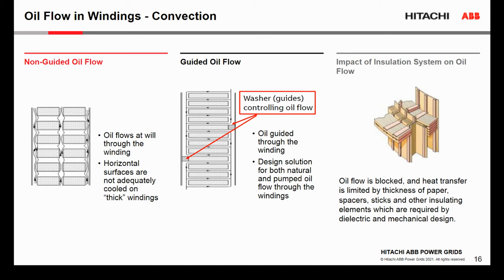In smaller windings rated for smaller MVA, or windings where the current density is rather low, we use only vertical oil ducts around the windings to dissipate the heat and reduce the temperature of the windings. But in the main windings, like high voltage and low voltage windings, we have much higher losses, and also the radial build is much greater. So the vertical oil ducts are not sufficient to dissipate the heat.